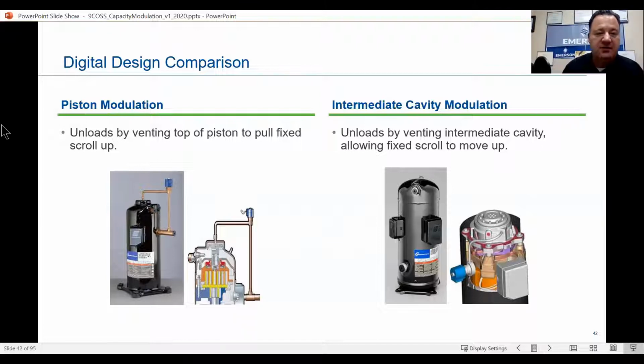On the left-hand side, we have the smaller model. As I said before, it unloads by venting the top of the piston to pull the fixed scroll up. You can see all the solenoid and the copper tubing is on the outside of the scroll. This is not a handle, by the way. Please do not pick it up by that, okay? This solenoid valve has been tested over 3 million times, so you can't just replace that with any old solenoid valve, and this will all be in your specs. But you can see what it's doing here, okay? It's bleeding off that gas at the top and allowing that fixed scroll to lift up that 1 millimeter.